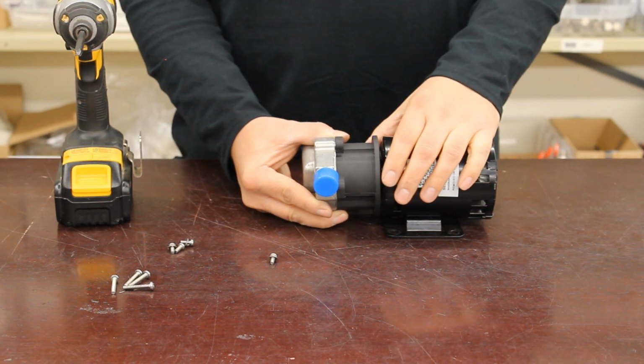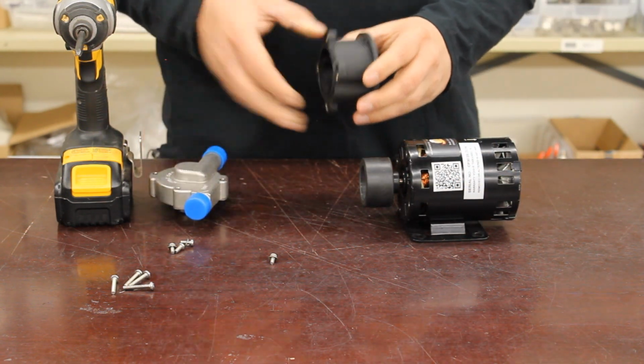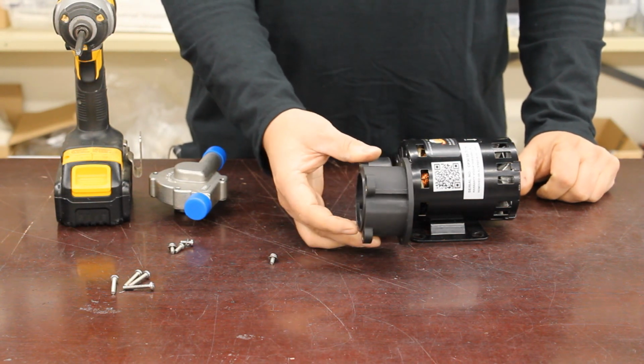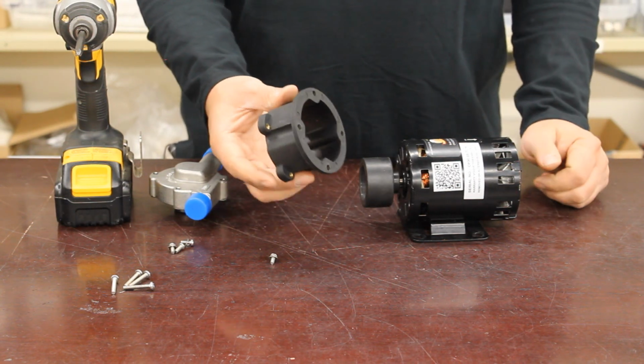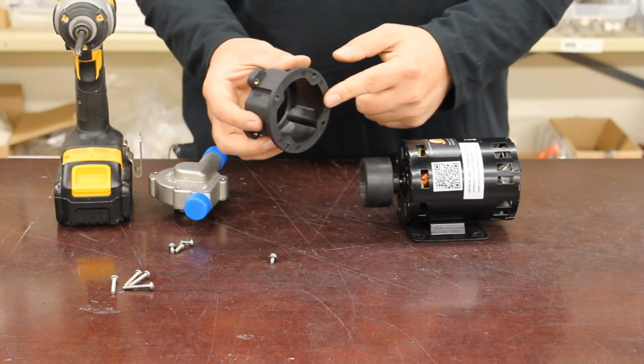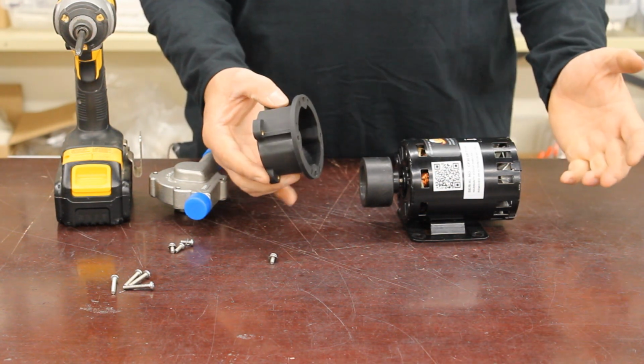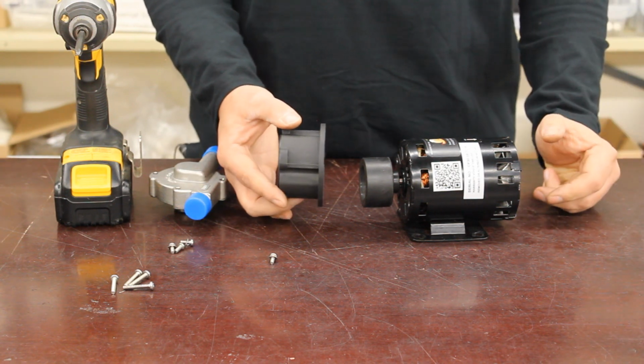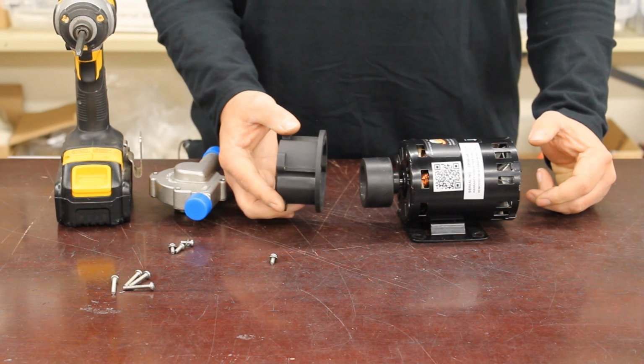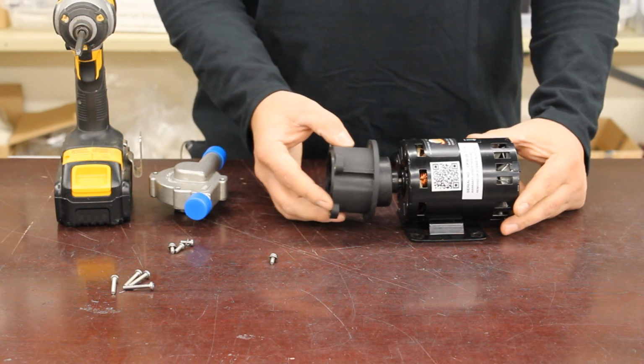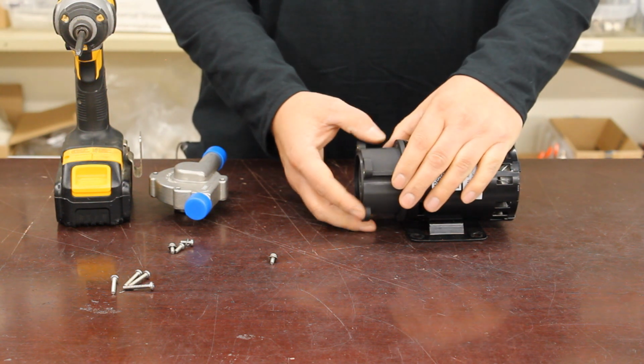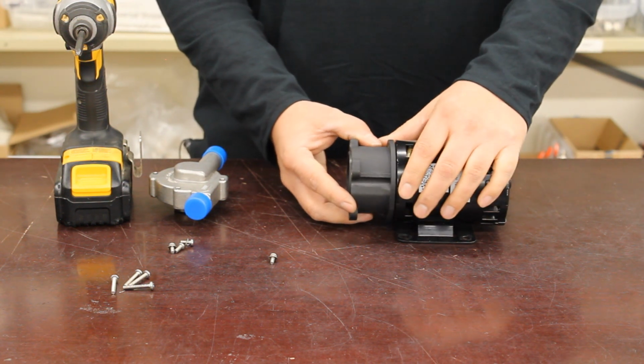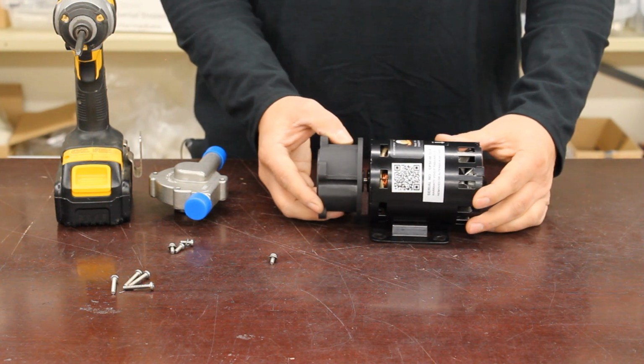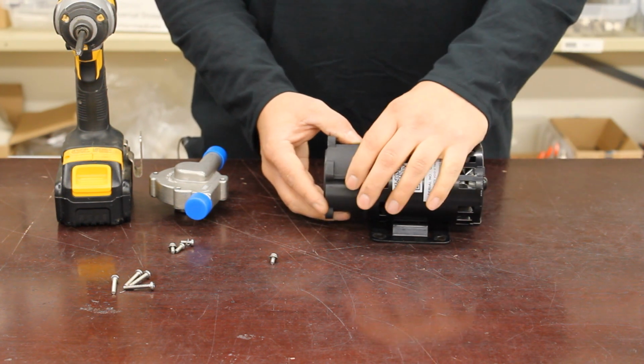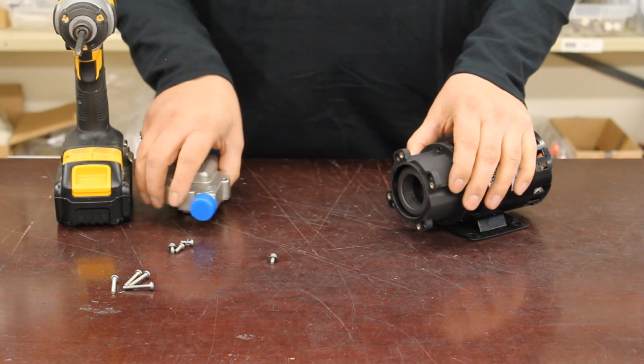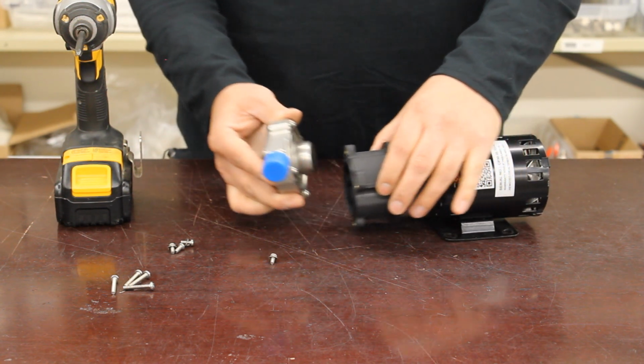One of the primary reasons why this may happen is where a user takes the mounting ring off of the motor and cuts a similarly shaped hole and series of holes into the side of any kind of material, whether a toolbox, some kind of enclosure, or a custom mounting bracket, and then sandwiches that material between the motor and the ring for mounting purposes. When you put any spacing or gap between these two components, it retracts the cup magnet back from where the head has to be positioned.